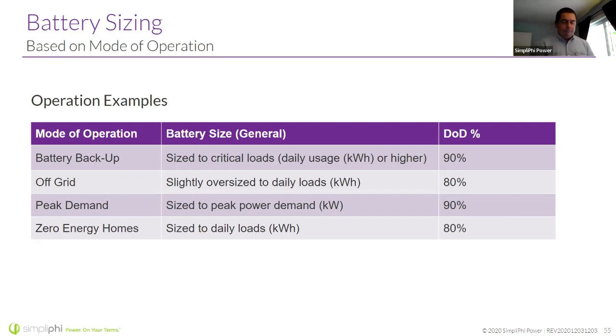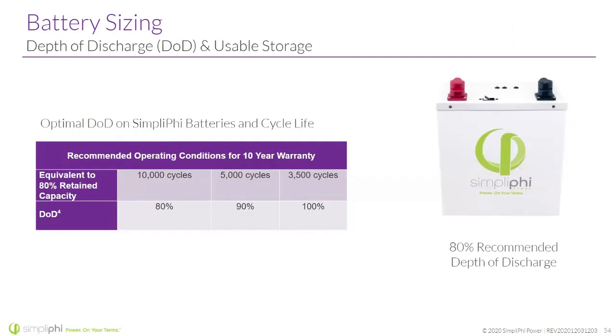So Chuck, if you don't mind going back to that previous slide just for a second, and I know that we're running out of time here, but a couple of people asked about this in the Q&A. So it's important to point out here that there's a drastic difference in the number of cycles, the number of kilowatt hours you can put into and take out of the battery when you're only discharging down to 80%. Now, keep in mind, these numbers are based on only cycles to 80% depth of discharge, right? We know that all homeowners are probably going to have a mixture of different cycles, but this goes to show you what we expect out of a battery.